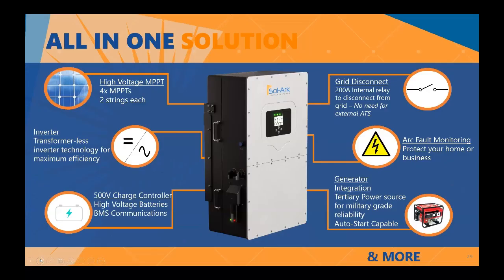The first thing we need to know about these new inverters is that they are all-in-one solutions. With the 30K, the first important aspect is the high voltage MPPTs. With this, you have the capability to distribute 39 kilowatts of PV into 4 MPPTs with 2 strings per MPPT. We'll jump into more detail in the next slide.